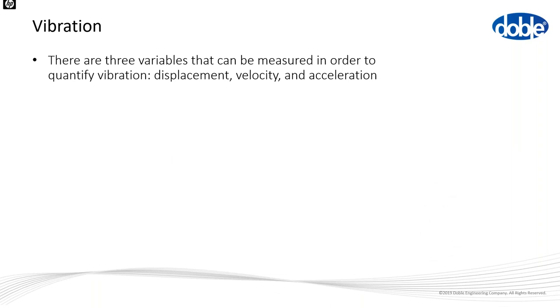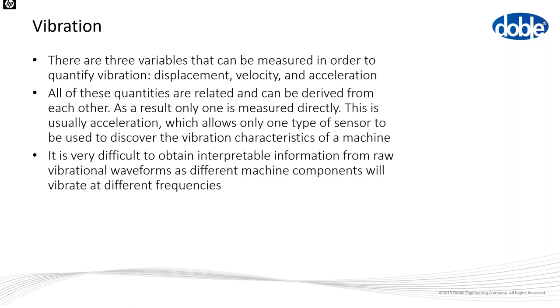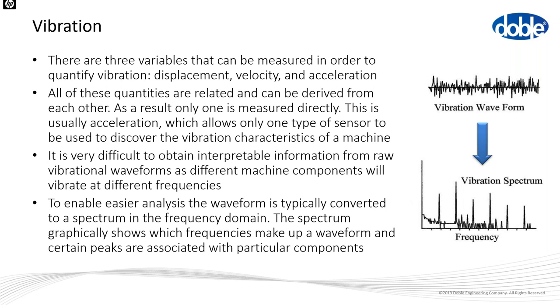Three variables are monitored to quantify vibration: absolute displacement, velocity, and acceleration. All are related and can be derived from each other, so we typically only measure one — usually acceleration, using a small accelerometer. Raw waveforms can be quite noisy and difficult to interpret, so we typically convert the raw waveform into a frequency domain graph, similar to our EMI and motor current signature analysis techniques.